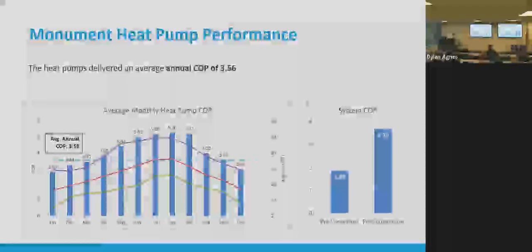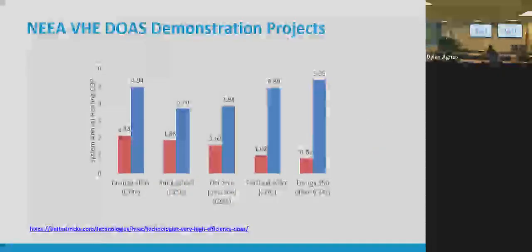This is something that I always love to do anytime we have enough data: calculate the overall system performance in a commercial or a school application. Basically, sum up all the loads, the envelope loads and the ventilation loads, and divide by all the energy inputs, to give you the whole system performance, how well it performed. Make it dimensionless so it's a COP and it's easy to consider. Before, they had a total COP of about 1.88. That's better than a lot of electric resistance because cooling has higher performance and some of it was heat pump to begin with. But we have a system COP of 3.7. So in that relatively cold climate, just remember that 3.7 number is the system level COP. I'll get to a reason why that matters in a minute.